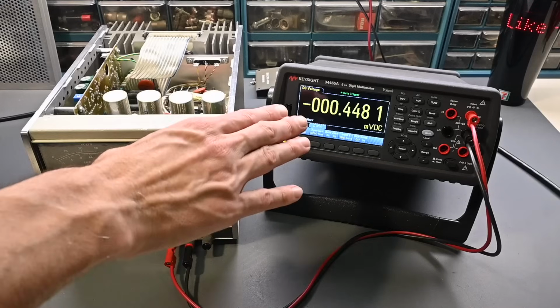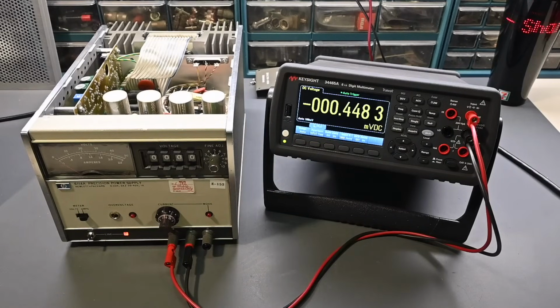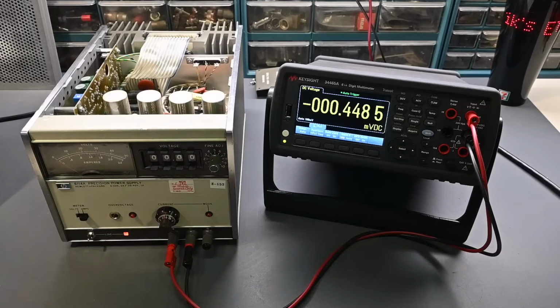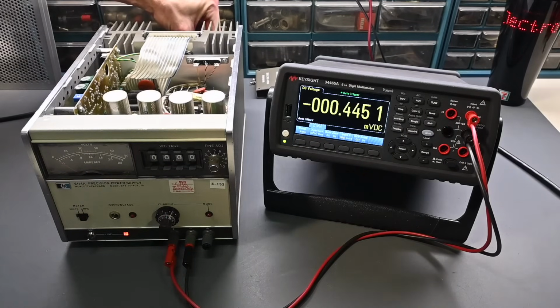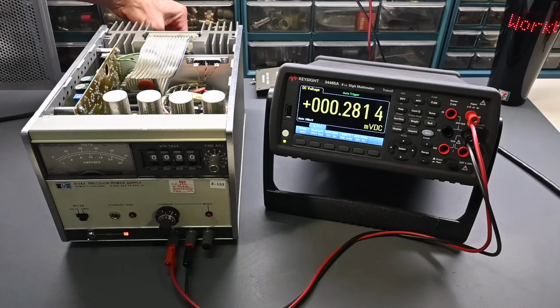And it's been very stable now for, I'd say, about 15 or 20 minutes. It's not drifting around or changing much other than a microvolt or two, but no significant changes. And the power supply has been on for over an hour. So it looks very good. Not seeing any problems there at this point with that calibration. So I'm going to remove this jumper wire back here. The purpose of the jumper is to disable the voltage control circuit. So let me just get that off of there.